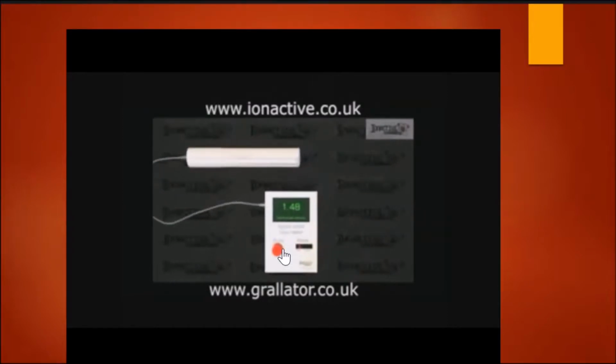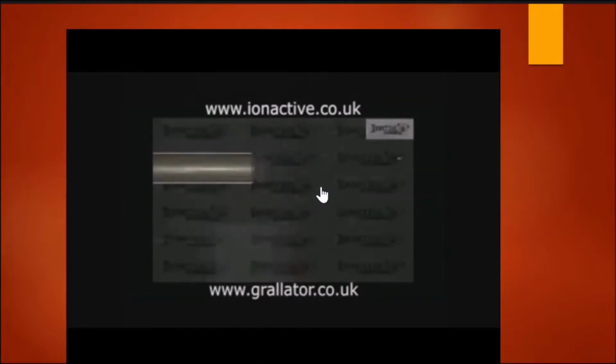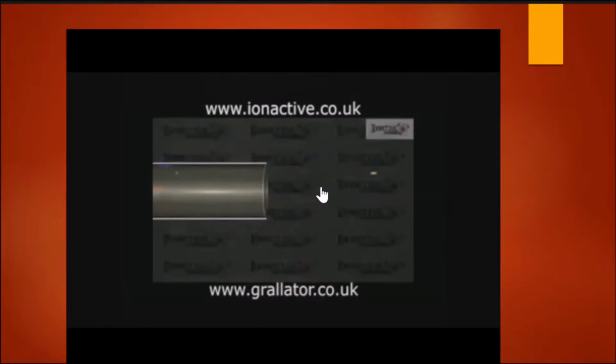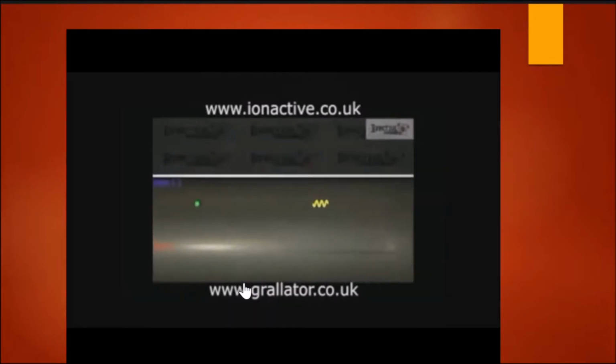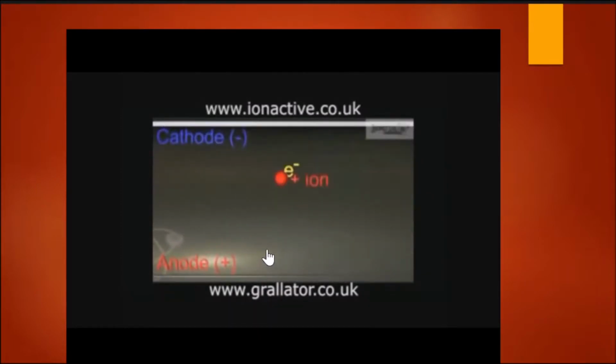The tube works on the principle of gas amplification. Here we go. Here comes some incoming ionizing radiation. It ionizes some of the inert detector gas, resulting in a free electron and a positive ion. Okay, so what's going to happen is this electron is going to be attracted to the wire, and that's going to alter the voltage. And you have it.